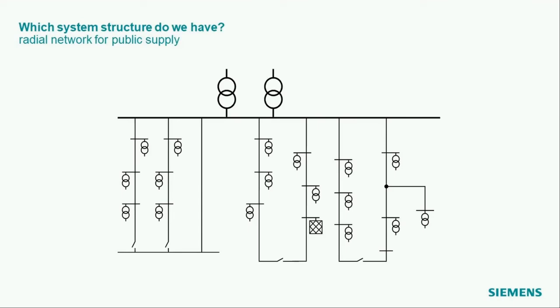You may ask the question now, why do we have these strange connections here on the bottom? The reason is the following. Imagine you have one cable destroyed, for instance by street work. In the moment the cable is destroyed, you typically have a short circuit. Then the protection will disconnect this cable to remove the short circuit. But then the bottom transformer here is without energy. What you can do then is remove the destroyed cable from the network and then close this connection point here on the bottom and resupply this transformer through the connection from the other side.